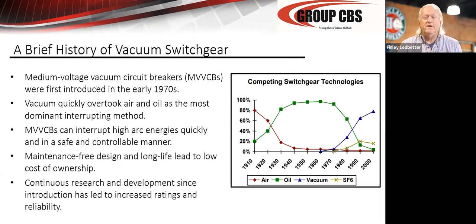And it's really the lifeblood and the infrastructure that keeps the power on. I challenge you to find many circuits, many applications, that the energy does not pass through a medium voltage circuit breaker at some point before it's utilized. So, the vacuum breakers were first introduced in the 70s. Now, vacuum breakers were built back in the 20s and 30s with limited success as far as interrupter rating goes. But in the 70s, GE, Allis Chalmers, Westinghouse, and some European and Asian manufacturers found ways to increase the interrupting capacity and to pack it into small light mechanisms and build compact vacuum draw-out circuit breakers. So in the 70s, you started to see air breaker technology and oil breaker technology fade.